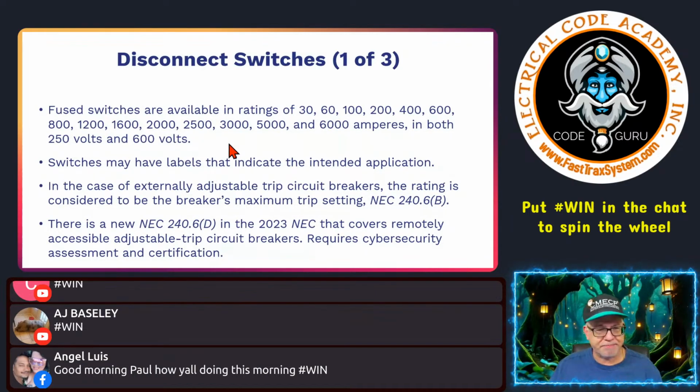I cannot complain. So when it comes to this, I don't worry about the 600 volt rating if I'm dealing with a 30, a 60, 100, or even a 200, let's say, on a 120/240 volt system. Now, once I start dealing with 277s, 480s, and whatnot, as you get further up into these frame ratings or fuse sizes, then you start worrying a little more. Obviously, you're going to have to be aware of the voltage ratings that you're dealing with.